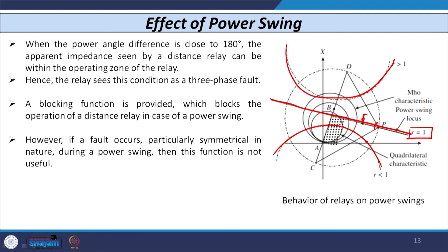In any case, you can see the locus always passes through the 3 zone characteristic of the distance relay, whether it is the quadrilateral or the Mho type characteristic. If I consider the quadrilateral relay, then any of these characteristics first enters the third zone of the Mho relay, and then it enters the quadrilateral relay third zone. Because of this, maloperation of the distance relay is possible, particularly in the third zone. So, we need to again take a corrective measure, and that is normally in terms of a power swing blocking function.